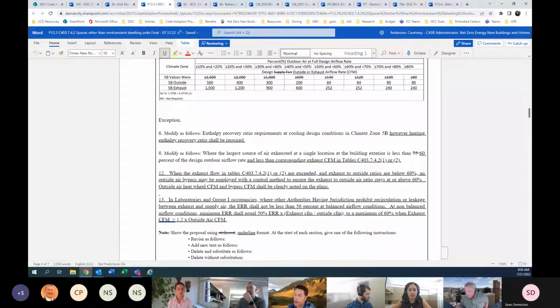So the higher the enthalpy recovery ratio, the higher the pressure drop, which is fine, except that obviously you can, say an average system has 2 inches external, but your system has 1, you can chew up that extra inch in a fan power allowance, because the brake horsepower is just brake horsepower divided by CFM, and that's what you get. And so, if you have a really short duct, say you're 1/10 of an inch, you could put in a really bad heat exchanger.